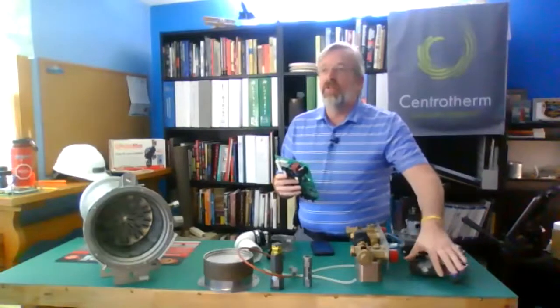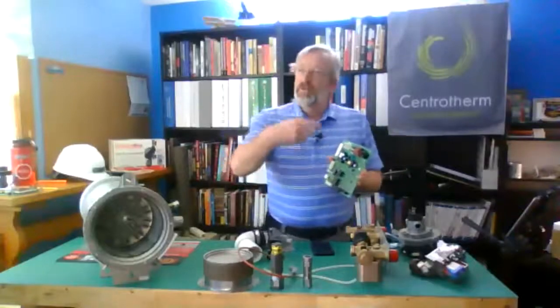If I've got spark here, all right, this is okay. If I don't have spark here, real quick, I just identified I don't have spark. I got a problem in my ignition module. Now I'll tell you that's a pretty infrequent flyer for these boilers, is that ignition module. But on a residential boiler, you get 4 tries for ignition. So if you've really done this right, your very first try for ignition, you're going to determine your gas pressure, volume, and does my gas valve open. Your boiler will go through a post-purge, pre-purge.